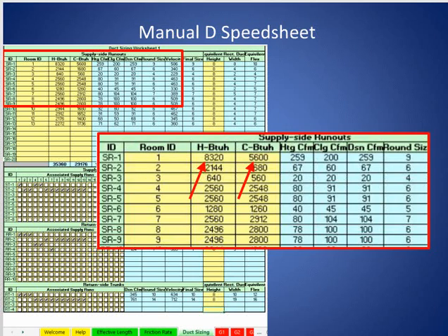Wait a minute — where did those numbers come from? Those numbers are given to us by a designer who has done a Manual J load calculation. The end point of that whole design is to figure out the heating and cooling BTUs per hour required to heat and cool a room. And the blue fields on the right fill out automatically — we get a heating CFM of 259 and a cooling CFM of 200, based on the total air flow of the whole system recorded elsewhere on the sheet, which was based on a Manual S equipment selection process for picking heating and cooling equipment that meets the Manual J load.